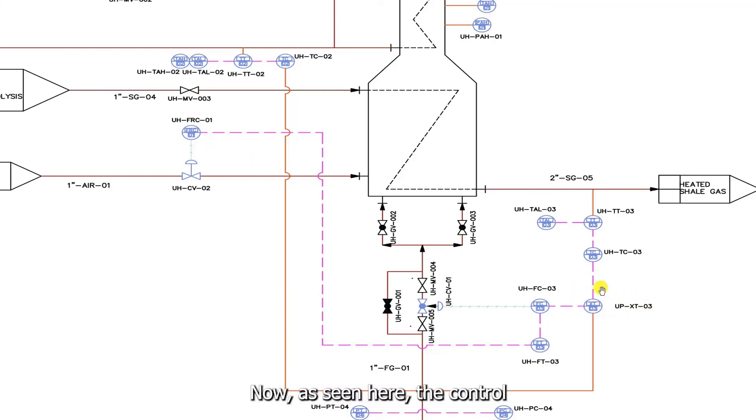Now, as seen here, the control loop performs a logic function on the two temperatures. The function is tagged XT-03. The present piping and instrumentation diagram does not indicate the nature of this function, but an educated guess is that this logic function is a comparison function. It takes the higher temperature measurement for the purpose of control.